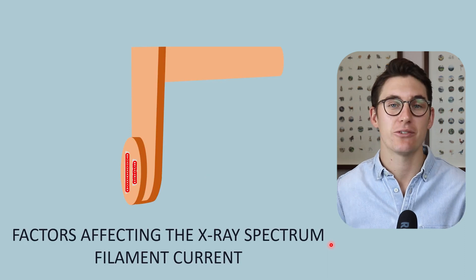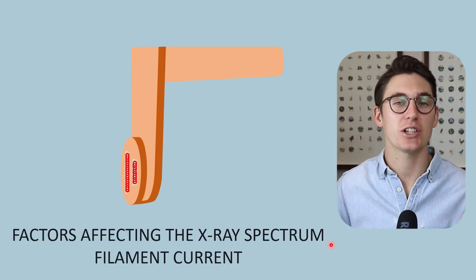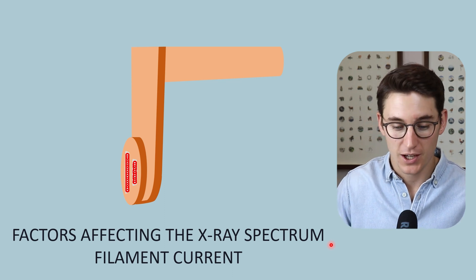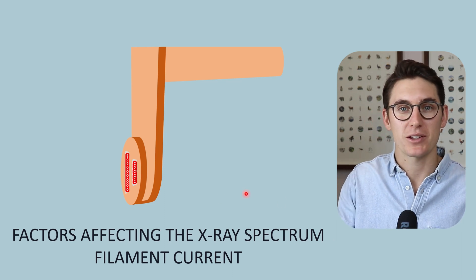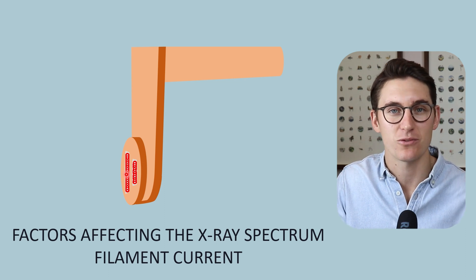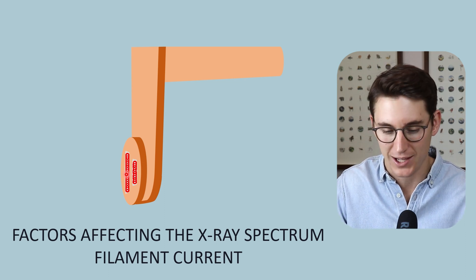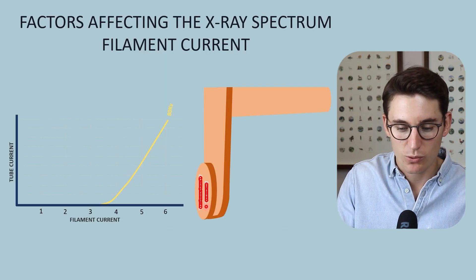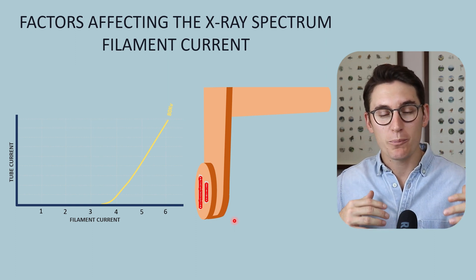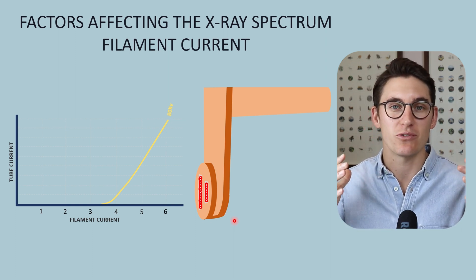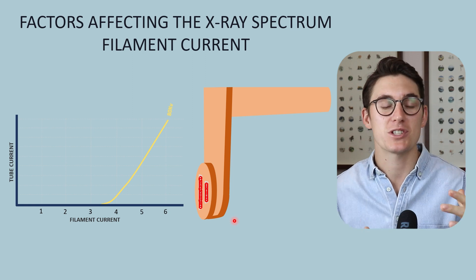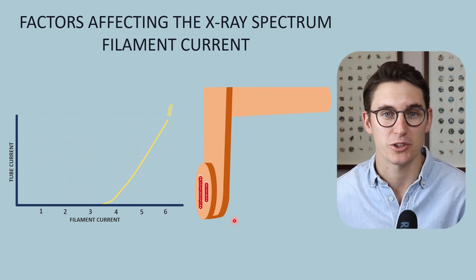Let's start with the filament current and see how changing it affects our x-ray spectrum. When we're talking about the filament current, we are talking about the current that we run through our tungsten filament on our cathode. When we run current through this tungsten filament, we make electrons available on the surface of that filament in a process called thermionic emission.